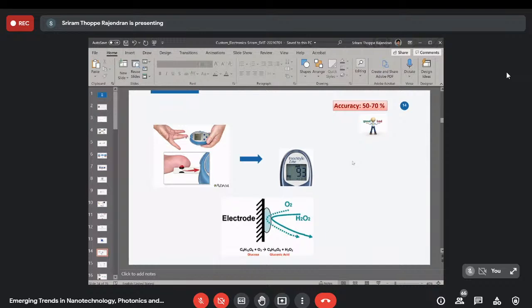However, I have to say that the accuracy of this glucose meter is not really high. It's between 50 to 70%. There are pros and cons, but for a glucose meter you don't have to be accurate. What you are interested in is knowing the changing levels of glucose in your body. That's the most important aspect of the device. You have different use case scenarios, and different levels of accuracy required. So you don't always have to be accurate in point of care diagnostics. In this case 50 to 70% accuracy is fine. What you want to see is just a change in the level.